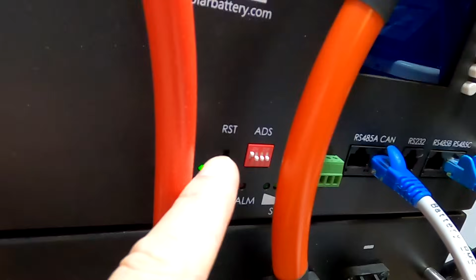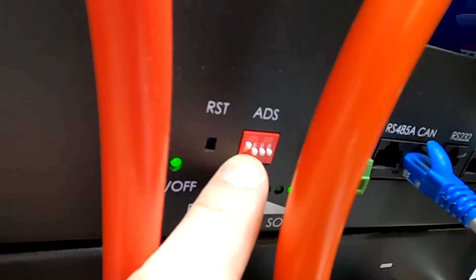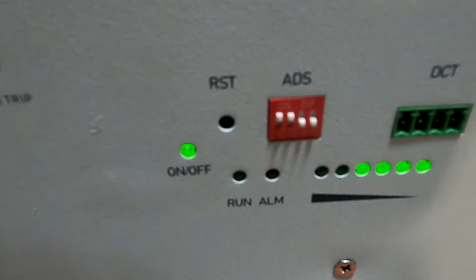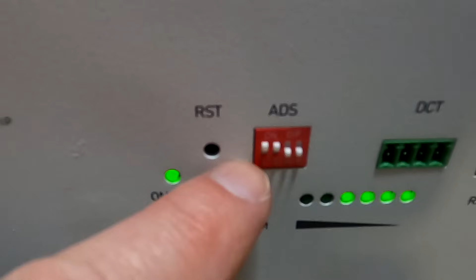And you may remember from a past video when we set this all up here, we changed the ADS, the dip switches here, accordingly. So this is battery number 1, this is our master. This is our battery number 2. See, dip switch number 2 is on. And down here, the Global Power battery is our battery number 3, which has dip switch number 1 and 2 on. So 1 plus 2 is 3.